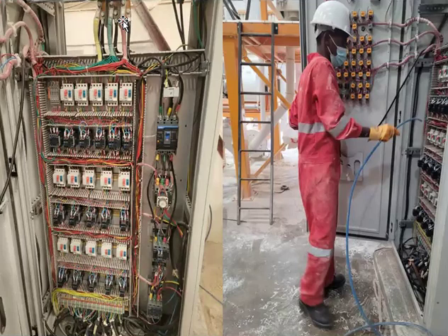these are the control circuits, as you learned maybe in workshop 1, workshop 2. As these motors are starting to run, they draw a lot of current, and usually there are sparks in this control panel. So you have to always monitor the spark not to exceed the normal spark that we always expect as it changes from star to delta.